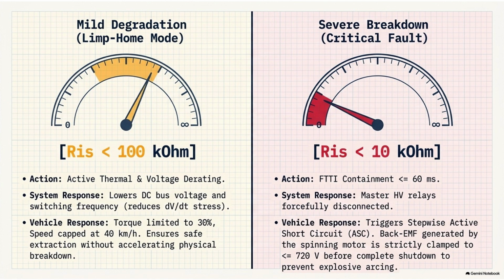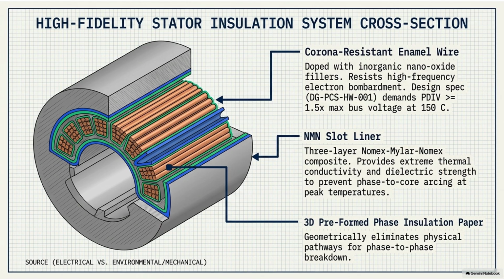The architecture uses a third diagnostic layer that is purely predictive, which is zero sequence voltage diagnostics. Yes. This is where the diagnostic software becomes incredibly elegant. This algorithm monitors the neutral point zero sequence voltage and the high-frequency common mode current of the inverter. What it is fundamentally looking for is a shift in the system's resonant frequency. Okay, here's where it gets really interesting. It's like tapping a fine crystal glass and listening to the pitch. Even before it physically breaks, if a microfracture develops inside, the pitch changes because the microscopic structure has weakened.